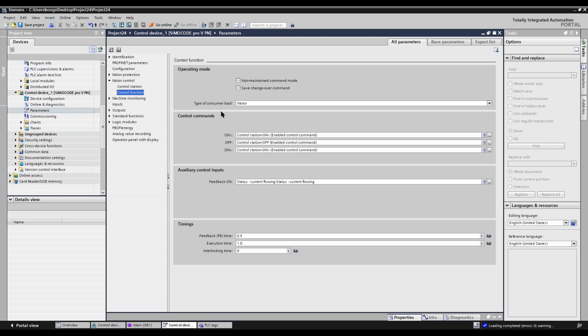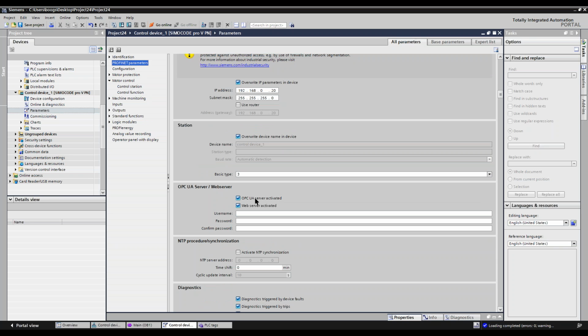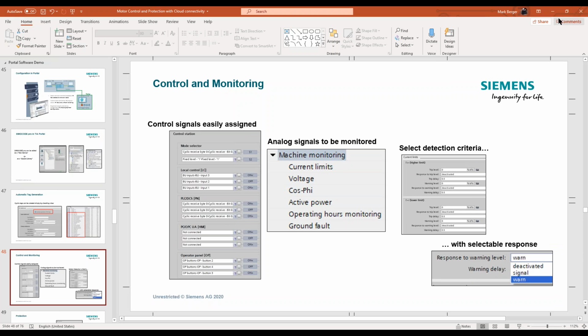We're running out of time. I hope this has helped a little bit, but I wanted to show you the cloud communication protocol, or cloud communications. So with these on the SIMOCODE, when we did the parameters, I turned on the cloud or OPC UA so that it can communicate to a cloud or to a historian. Well, I want to demonstrate that quickly. So what I'm going to do is, the SIMOCODE is an OPC UA server. OPC requires a client. So I have some software on my laptop.